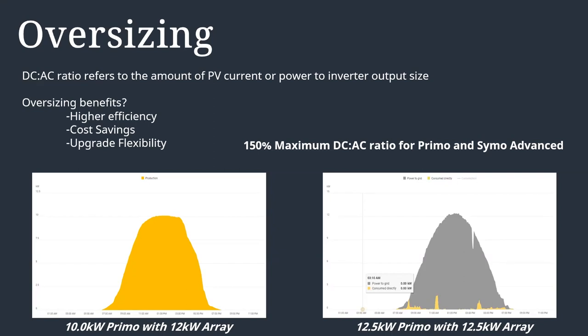Oversized systems are often much more cost effective. For the price of a lower power class inverter, you can support a larger array. Inverters with poor DC-to-AC ratio or no oversizing capabilities increase the cost per watt significantly. Another benefit to oversizing is not having to upgrade the AC load center to support a larger inverter — you can apply more solar panels to the structure without surpassing current limitations of the load center bus bars. In commercial rooftops and ground mount systems, oversizing reduces the number of inverters needed, reducing initial cost and operation and maintenance expenses, resulting in a better return on investment.